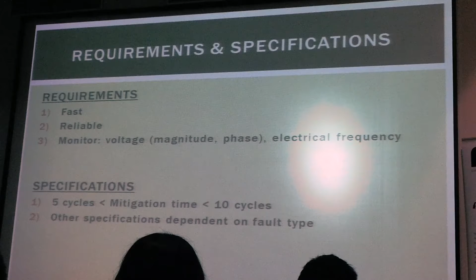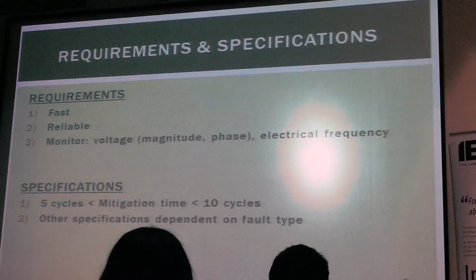The requirements for my algorithm were for it to be fast, reliable, and capable of monitoring a wide range of system parameters, including voltage, electrical frequency, and power angle. The specifications for my project depended upon the algorithm produced, but the most important one is the mitigation time. It has to be somewhere between 5 cycles and 10 cycles, which corresponds to 100 milliseconds and 200 milliseconds on a 50 Hz system.